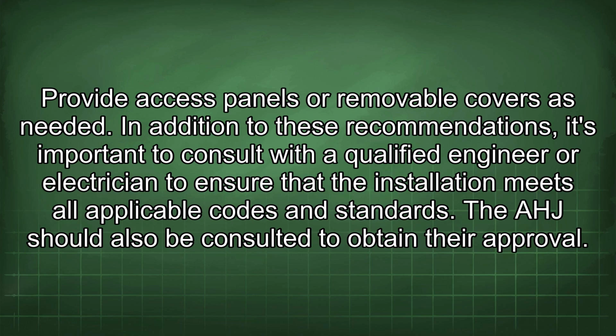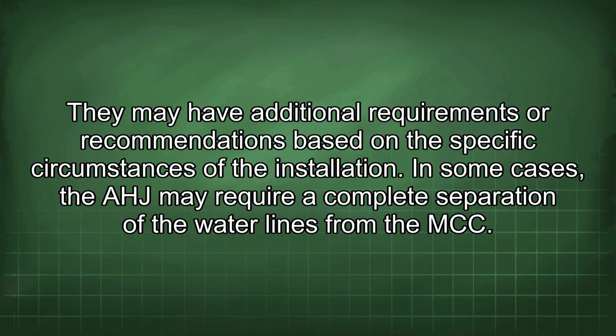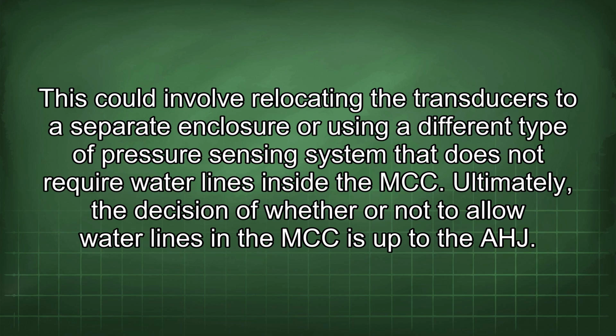In addition to these recommendations, it's important to consult with a qualified engineer or electrician to ensure that the installation meets all applicable codes and standards. The AHJ should also be consulted to obtain their approval. They may have additional requirements or recommendations based on the specific circumstances of the installation. In some cases, the AHJ may require a complete separation of the water lines from the MCC. This could involve relocating the transducers to a separate enclosure or using a different type of pressure sensing system that does not require water lines inside the MCC.